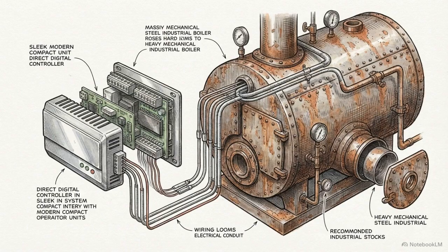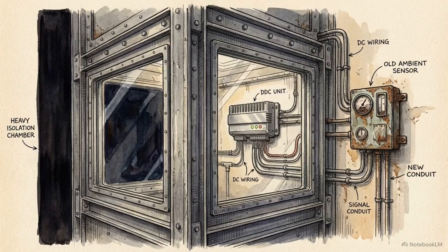The operational risk here is absolutely massive. Patching modern hardware directly into an old network can introduce data collisions, potentially destabilizing the entire building's current mechanical operations. The primary constraint is backward compatibility. The newly designed subsystem must enhance the facility's capabilities without breaking or overriding the existing DDC logic loops already in place.